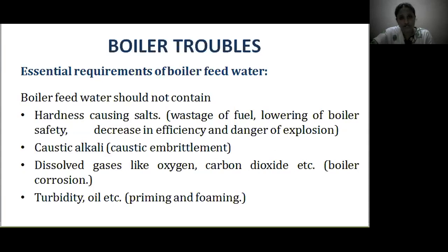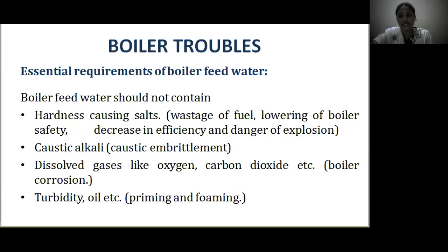What are boiler troubles? Before seeing the boiler troubles, let me explain what boiler feed water is. The water used in the boiler for the production of steam is called boiler feed water. Such water should be free from hardness-causing substances, caustic alkali, and dissolved gases like oxygen, carbon dioxide, nitrogen, as well as turbidity and oil.